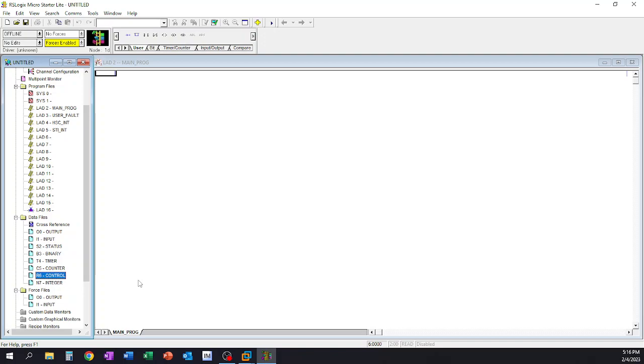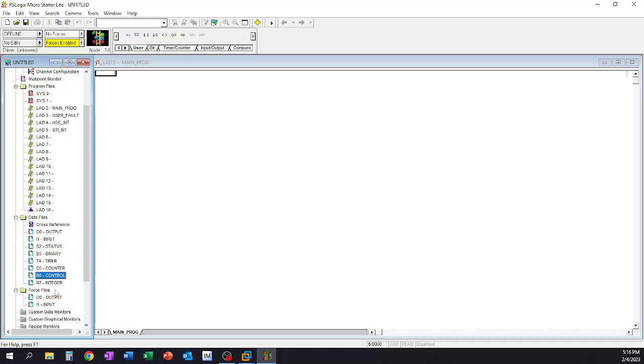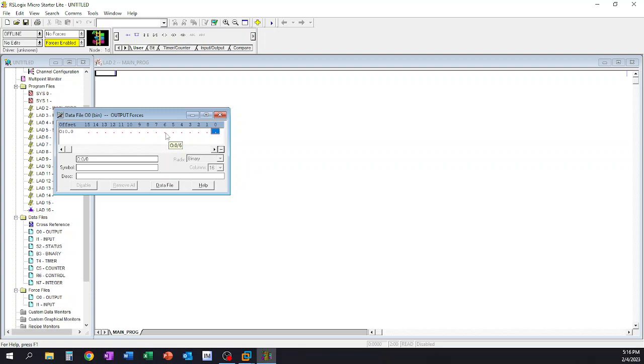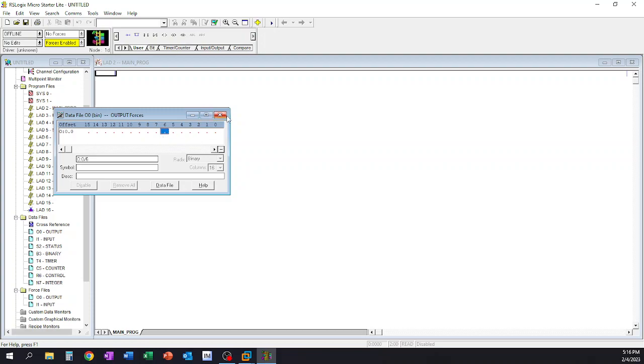Force files, those are generally where the processor would store your force. So if you go in and force an input or an output on or off, it's going to store it so that we can see it in our force files when we open it up. And what it would do is it would put like an X right here on where six is. So if we did output six right here, it would put an X in that slot saying that we'd force that position on.